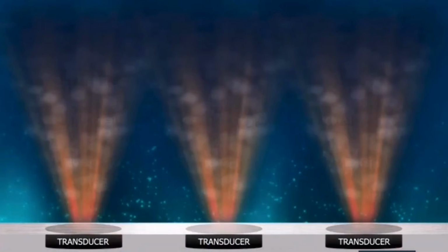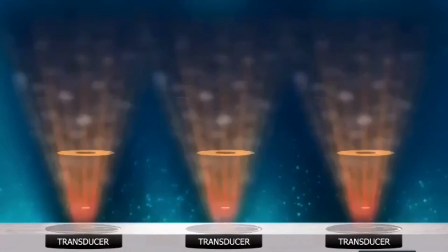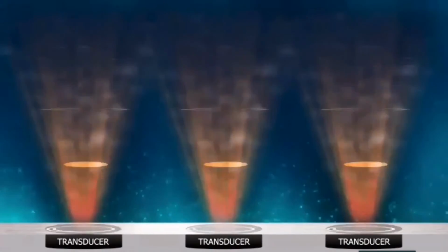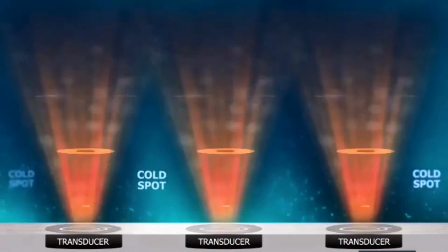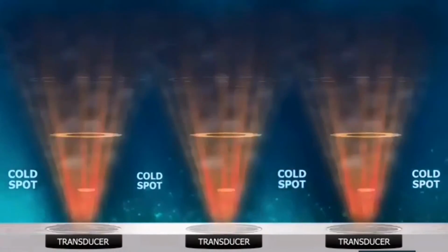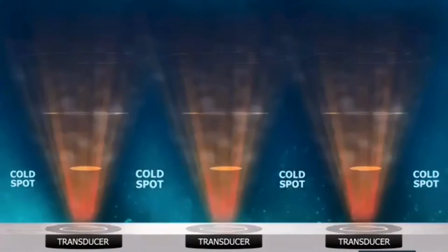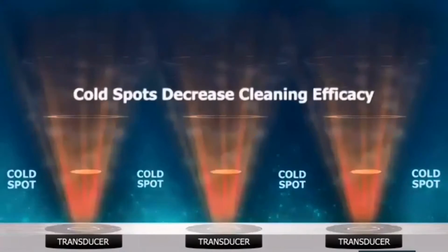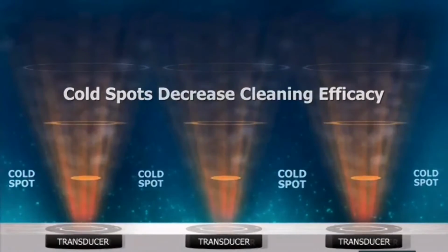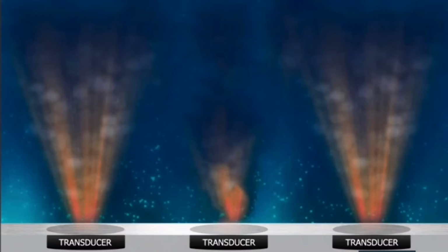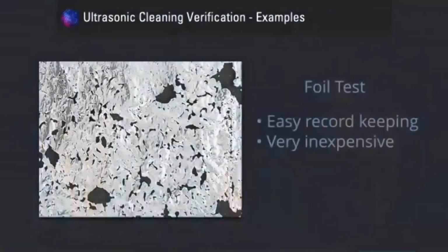Now, with regards to bonded transducers, there's something to take note of. When you have a machine with bonded transducers, you'll have your array of transducers that are bonded or mounted on the underside of your basin, and you have these cold spots that can form between them. And this can decrease the cleaning efficacy of your system, particularly if you have a bonded transducer that's failing and you don't even know it. So we need to do an inspection or a check, so that if we have a failing transducer, we know we need some service.